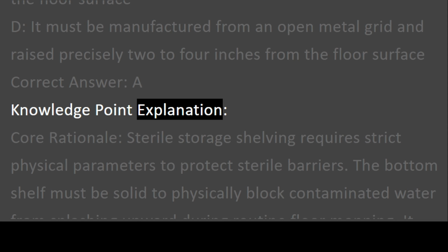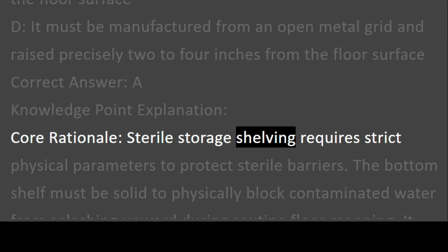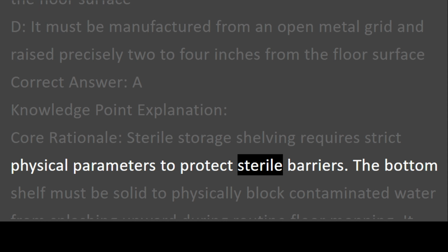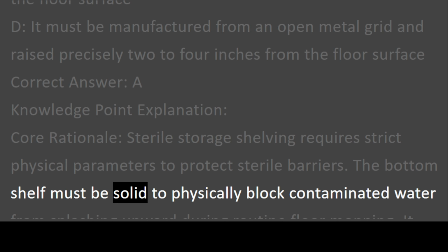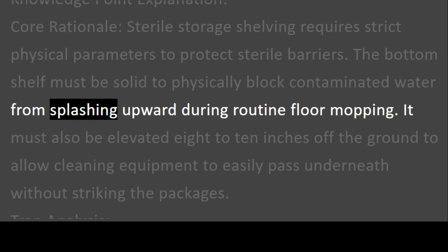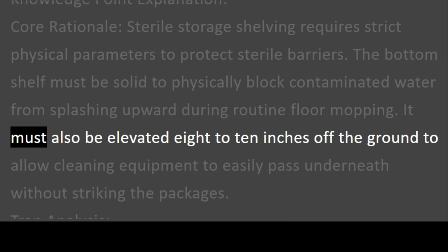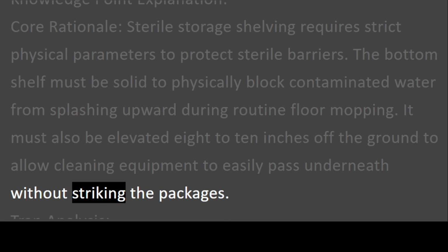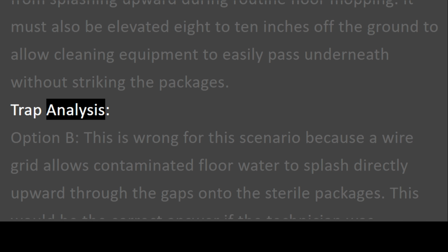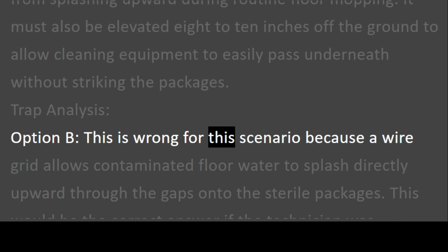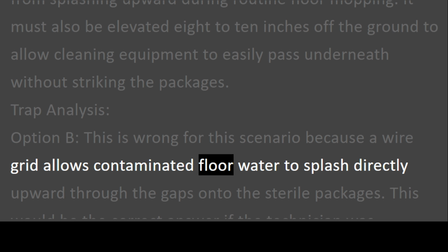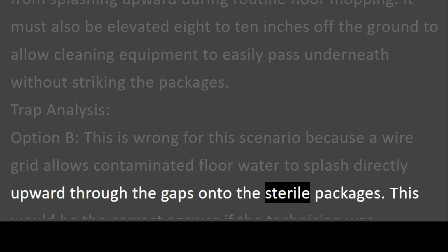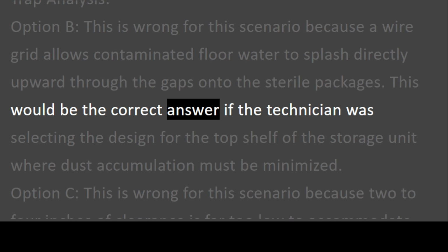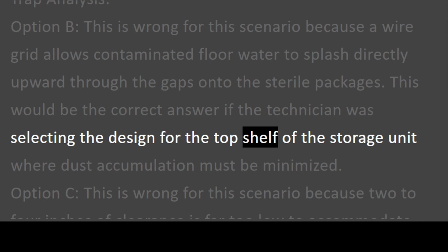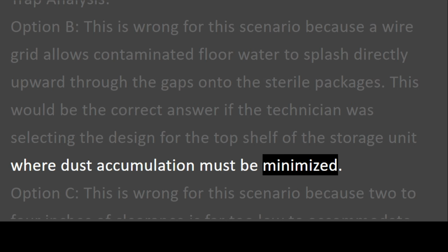Knowledge point explanation. Core rationale. Sterile storage shelving requires strict physical parameters to protect sterile barriers. The bottom shelf must be solid to physically block contaminated water from splashing upward during routine floor mopping. It must also be elevated 8 to 10 inches off the ground to allow cleaning equipment to easily pass underneath without striking the packages. Trap analysis. Option B. This is wrong for this scenario because a wire grid allows contaminated floor water to splash directly upward through the gaps onto the sterile packages. This would be the correct answer if the technician was selecting the design for the top shelf of the storage unit where dust accumulation must be minimized.